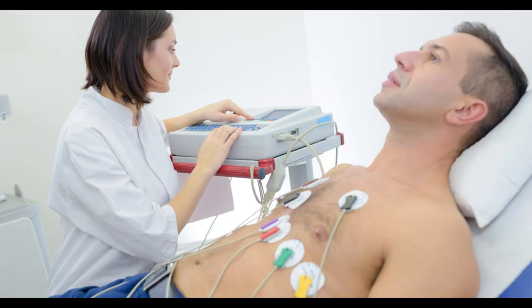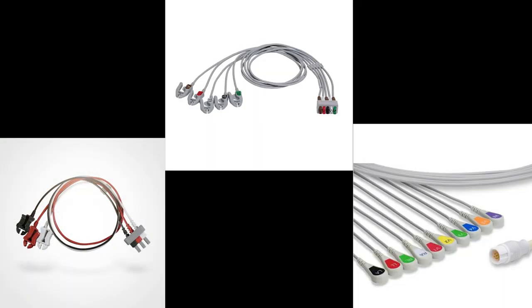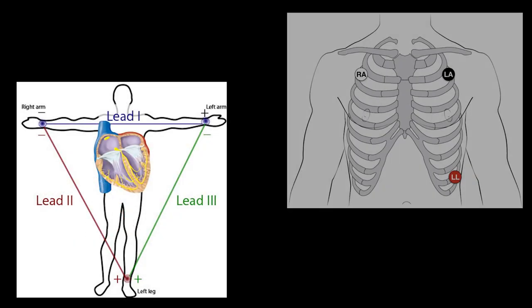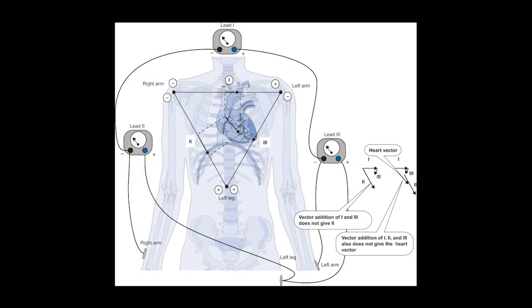There are three main configurations for detecting an ECG: three lead, five lead, and twelve lead, although two leads can be used to acquire a signal like on a defibrillator when using both paddles. Three lead is the most basic configuration where two electrodes are used to detect and one electrode is used as a reference signal. These are the standard leads one, two, and three — all part of something called Einthoven's Triangle.